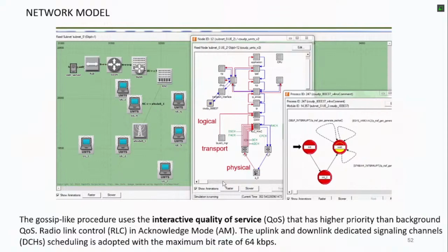I can show you a movie, but probably in the afternoon, that is just a representation. You see the packets of information exchanged between the units, and how these are elaborated inside the units within the physical transport or logical blocks, and this is the connection with the EMTP, so they give the information inside the EMTP. For example, the communication in our case is the phasor measurement, so they know the measurement of the phasor, the values of the voltage and the angle, and then the EMTP calculates the power flow, the reactive power, by using the previous equation, and injects or absorbs the variation of the reactive power. So I hope there are questions or something.